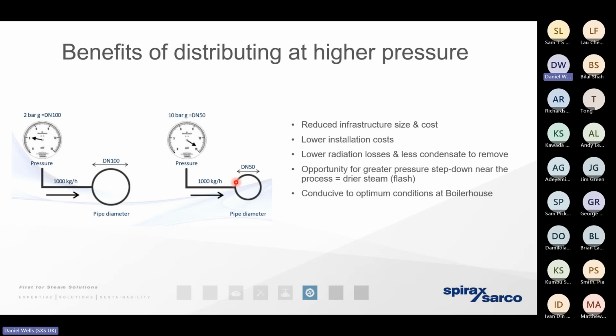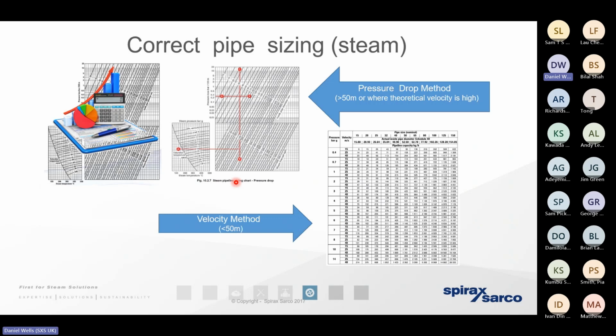And if we've got drier steam as a result of there not being as much condensate in the pipe, we've minimised the risk of any erosion, corrosion, water hammer. So we've reduced our burden of maintenance. And it also means if the steam's drier, there's more energy in it. So the boiler doesn't have to work as hard. And we're bringing the condition of the steam closer and closer to that red, dry, saturated steam line, meaning the heat exchangers and the process time, it's all going to work more efficiently. So pipe sizing is critically important.